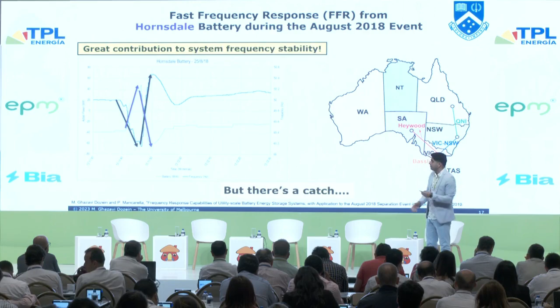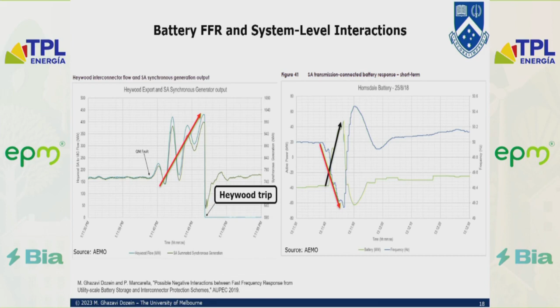But there is a catch. The battery is doing what it's designed for, but it provides this very sharp active power response. This results in a very sharp change in active power flowing through the interconnector, and this negatively impacted the stable operation of protection. So yes, the battery provides frequency control, but at the same time it resulted in the Heywood trip and South Australia separation.